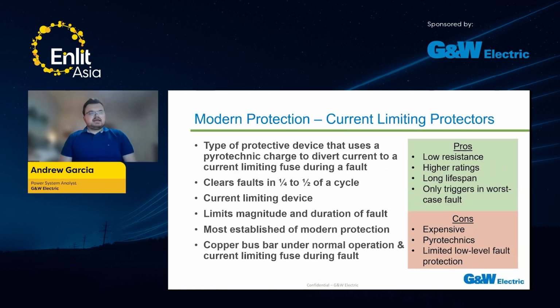And last but definitely not least, you have current limiting protectors. This is a very interesting device that uses a pyrotechnic charge to divert current to a current limiting fuse during a fault. You can think of it as the only thing on your system that you really want to explode. It clears faults in 1/4 to 1/2 of a cycle. And since it clears faults in a half cycle or less, it's a current limiting device. Similar to solid state breakers and current limiting fuses, it limits the magnitude and duration of a fault.